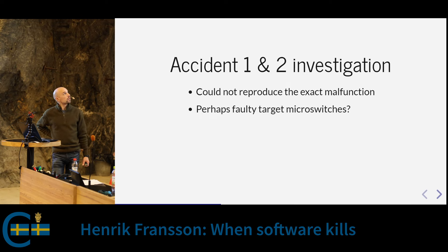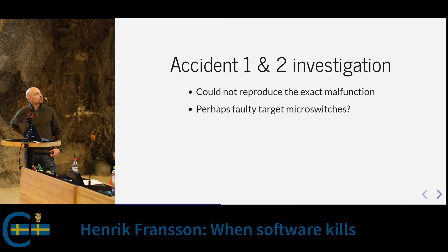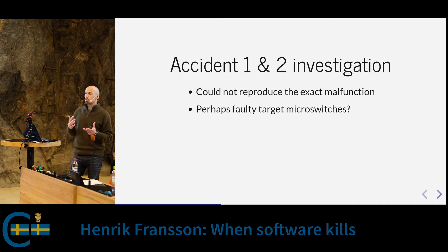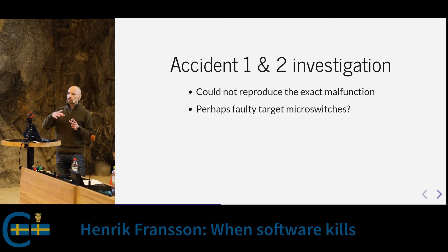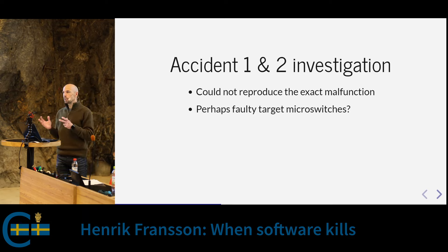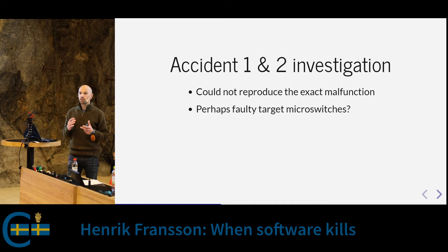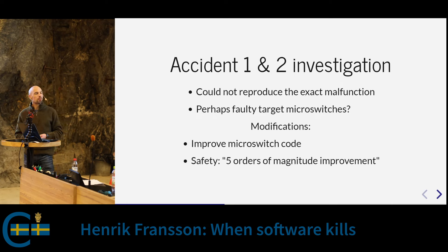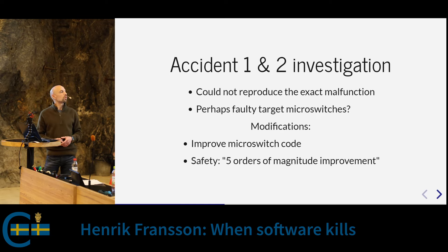Investigators were never able to reproduce the problem — neither the hospital nor the manufacturer. They started looking for probable causes and focused on micro switches — electrical switches sensing whether the metal parts were in or out of position. For redundancy they had not one but three micro switches, and they theorized there might be a malfunction there. So they improved the software a little to mitigate what they believed was the root cause.